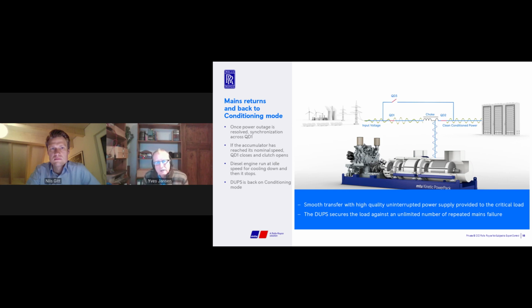Once the power outage is resolved, we have a synchronization across the circuit breaker QD1, the input circuit breaker. And if the accumulator has reached its nominal speed, QD1 closes and the clutch opens. The diesel engine will run at idle speed for cooling down, and then it will stop. The dynamic UPS, the MTU kinetic power pack, is back in conditioning mode. And then we again have a smooth transfer with high quality uninterrupted power supply provided to the critical load. The dynamic UPS secures the load against, which is very important, an unlimited number of repeated mains failures.